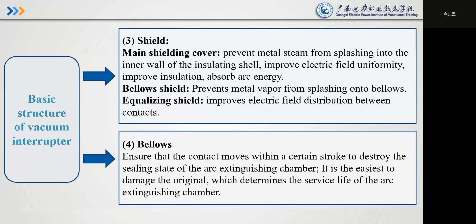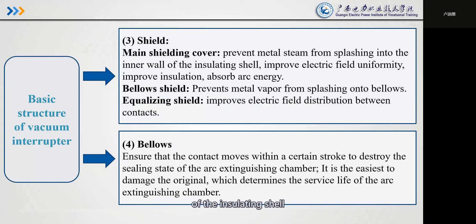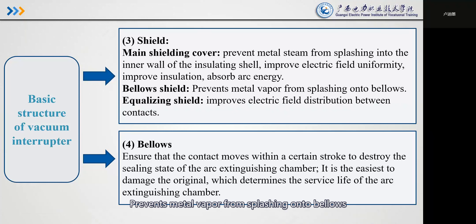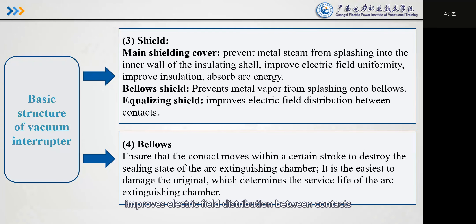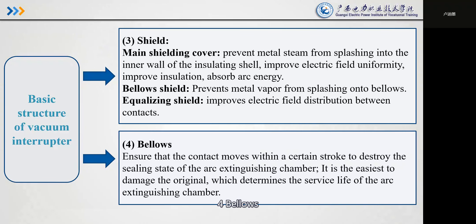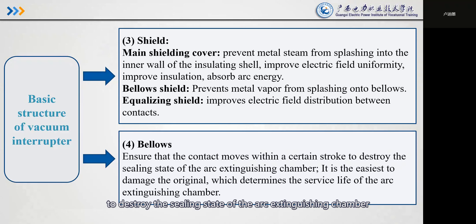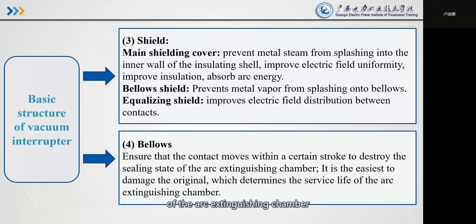(3) Shield: The main shield prevents metal steam from splashing onto the inner wall of the insulating shell, improves electrical field distribution, absorbs arc energy. The bellows shield prevents metal vapor from splashing into the bellows. The equalizing shield improves electrical field distribution between the contact parts. (4) Bellows: Ensures that the contact moves within a certain stroke to maintain the sealed state of the arc-extinguishing chamber. It is the most easily damaged component, and it determines the service life of the arc-extinguishing chamber.